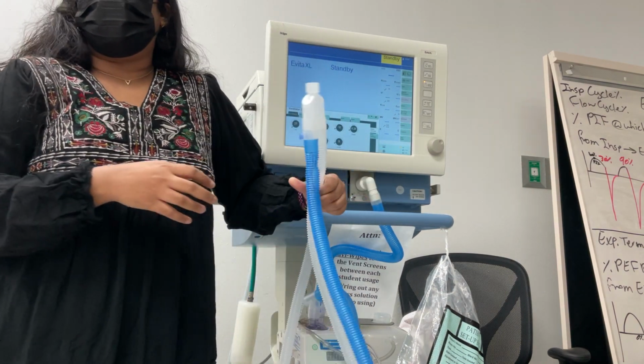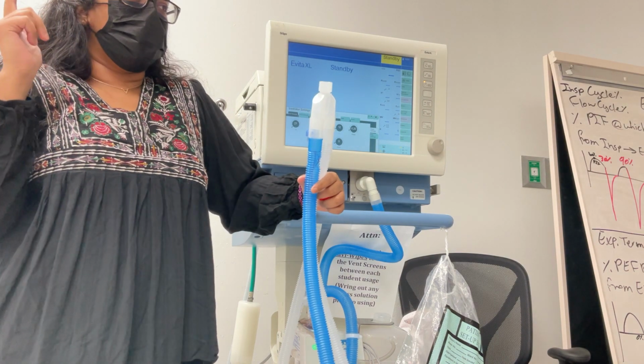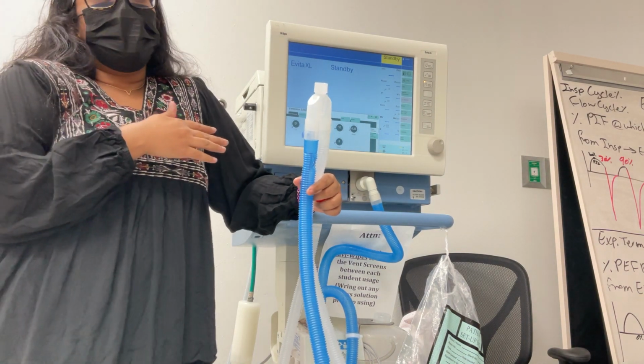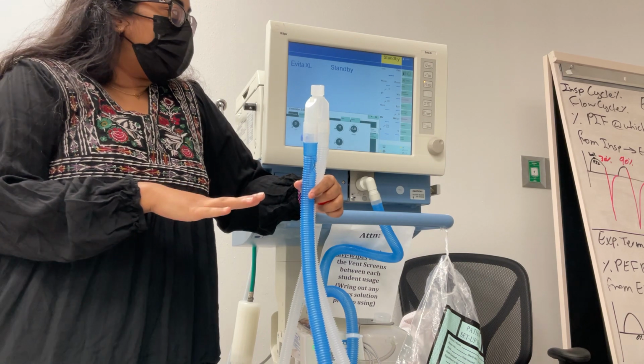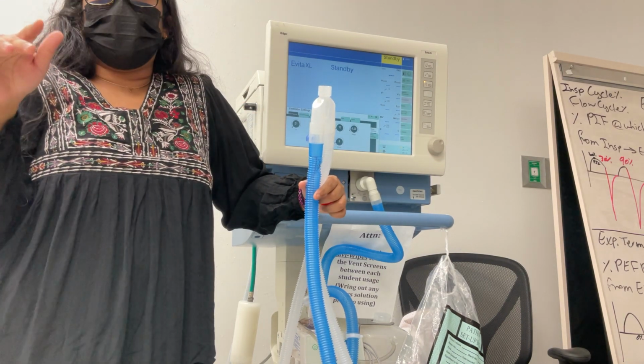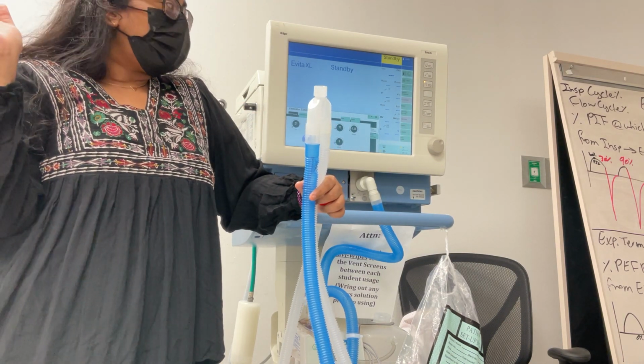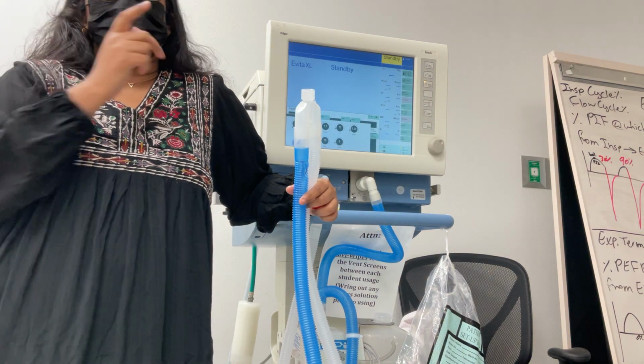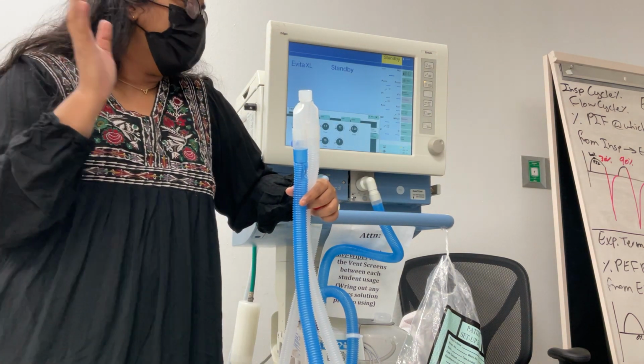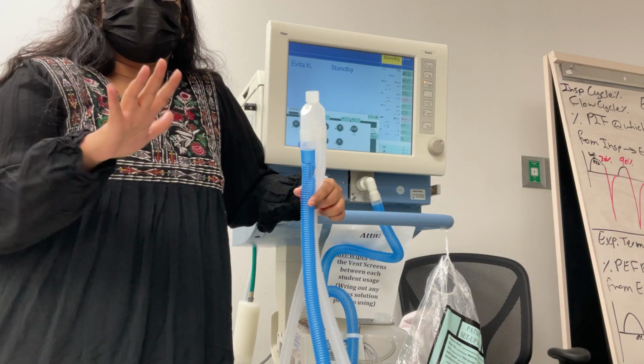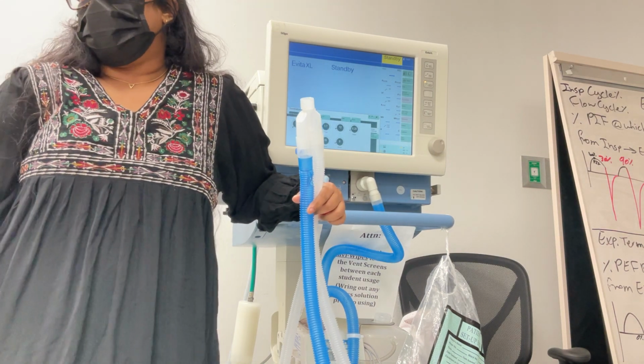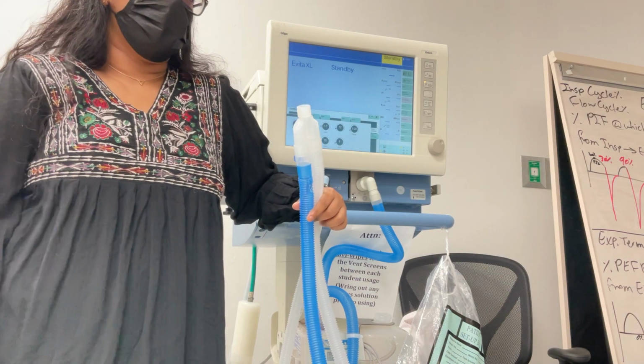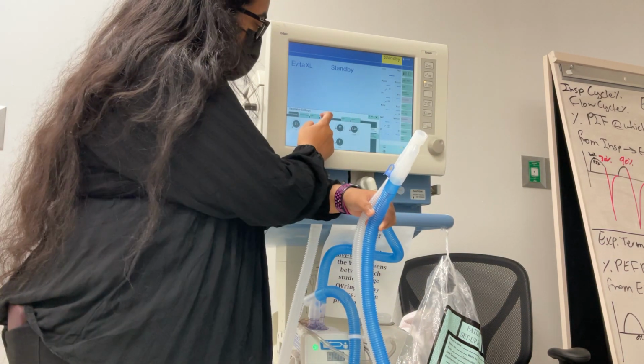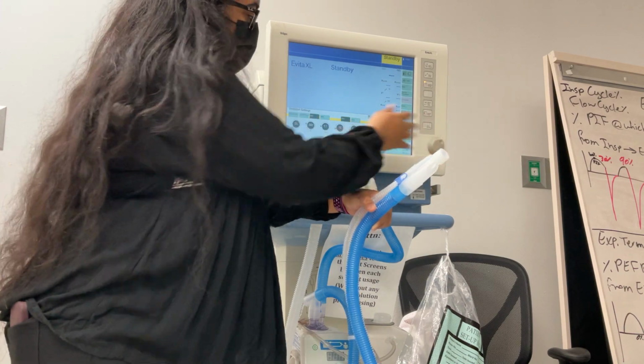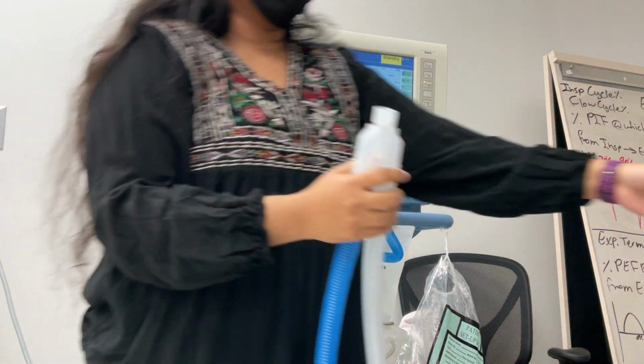I'm not going to go through like the simple modes like volume control, pressure control. Those are going to be the same on every ventilator. We'll go over the special names on this vent because this one has different names for volume control, pressure control, all that. And the additional settings like auto flow. This one doesn't have pressure volume guarantee. So little differences, but for the most part, the modes will all work the same. Volume control is always going to be volume control. Okay? So on this vent, volume control is actually CMV, and it's ingrained in us to avoid CMV because it's a control mode. We don't like it.